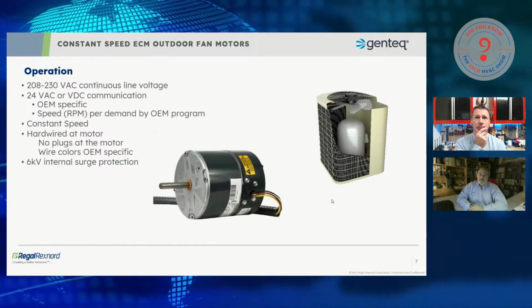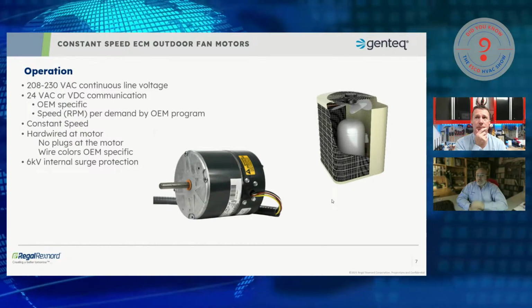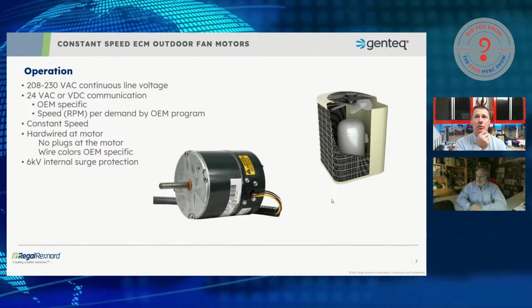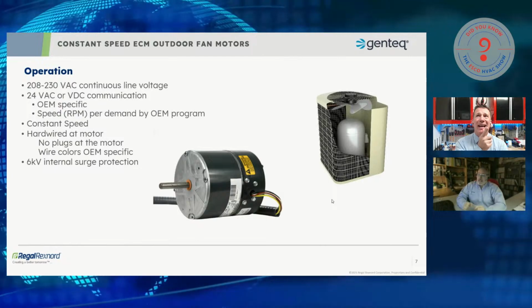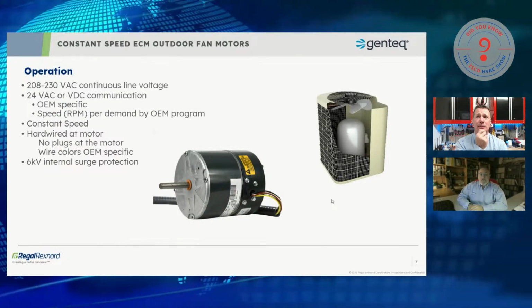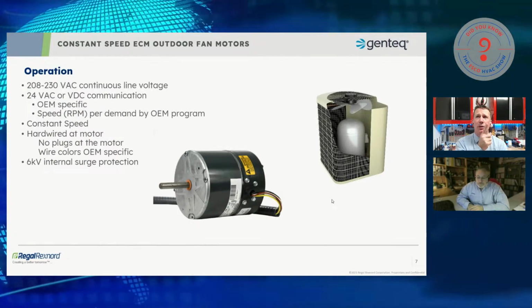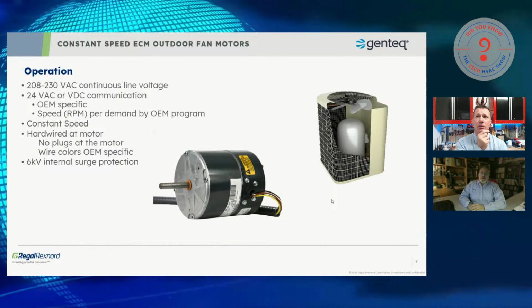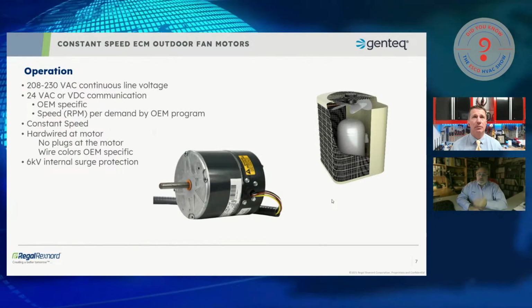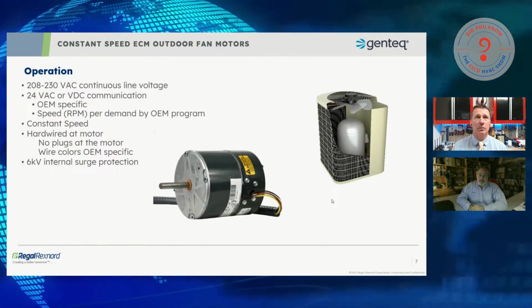All it cares about is maintaining the RPM of that shaft at whatever it's programmed to operate at. Are we using back EMF to calculate that? What's that? Are we using back EMF, or would you use any kind of a trigger on these? No, back EMF. So all of our ECMs are built with a permanent magnet rotor.